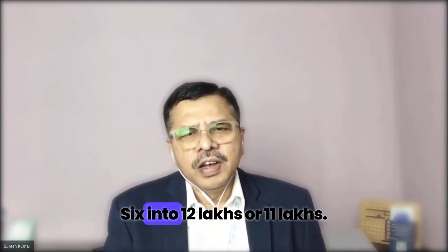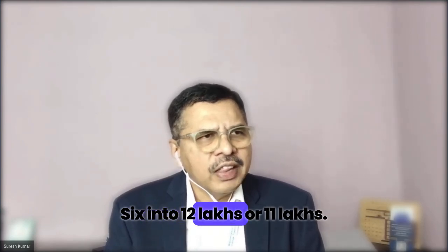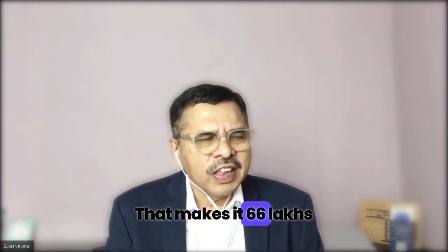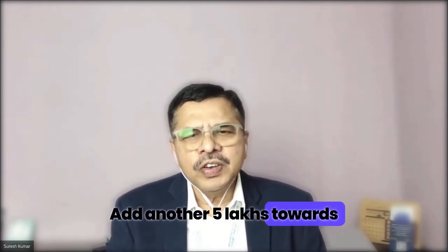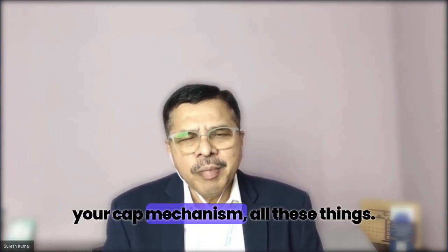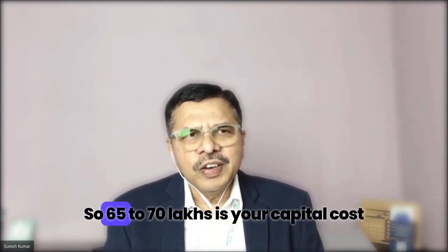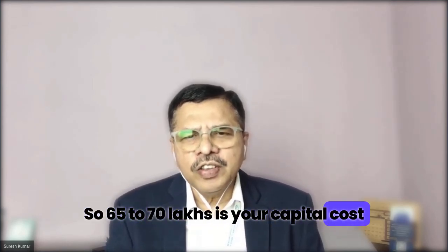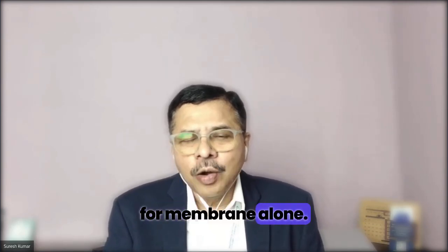6 into 12 lakhs or 11 lakhs. That makes it 66 lakhs is your membrane cost. Add another 5 lakhs towards automation, your PLC, then your valves, your CAP mechanism, all these things. So 65 to 70 lakhs is your capital cost for membrane alone.